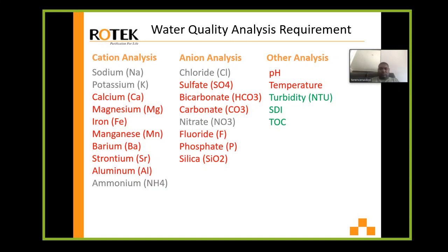Even municipal water supply uses flocculants. In tap water, if governments do not control the residual level of aluminum, an overdose of coagulants can cause aluminum to remain in the water. So aluminum can foul the membrane fast, and antiscalant cannot take care of aluminum issues.